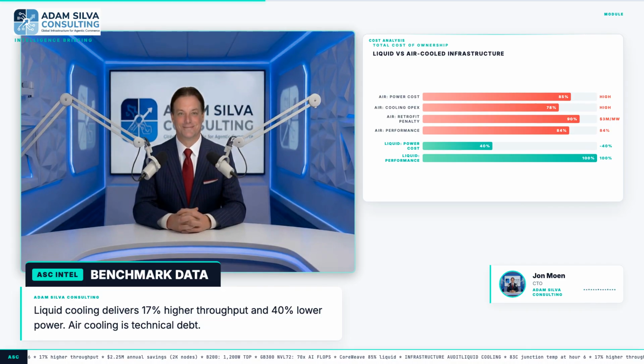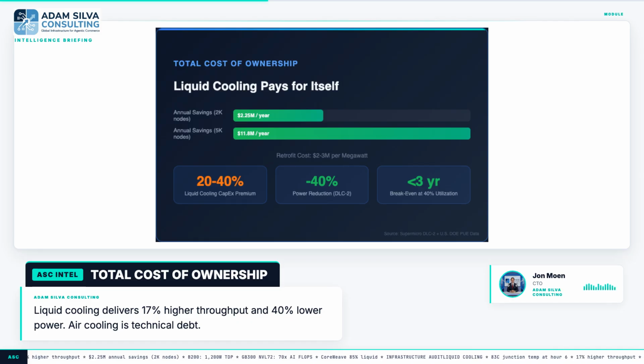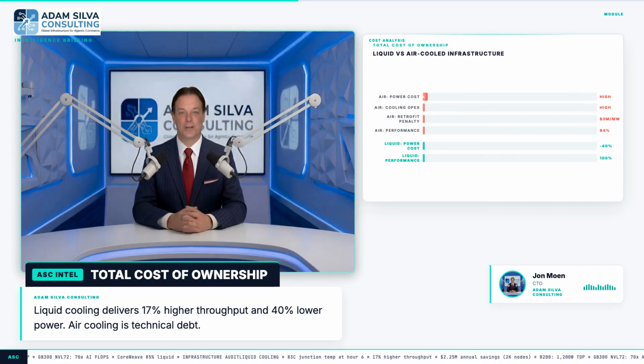That OPEX reduction closes the CAPEX premium on liquid cooling before the 3-year mark for any sustained workload above 40% GPU utilization. Is liquid cooling more expensive than air cooling? The upfront cost of liquid cooling is 20 to 40% higher than air-cooled equivalents, but the Supermicro DLC2 direct liquid cooling platform demonstrates 40% power reduction and 20% TCO reduction over a 3-year deployment horizon, making liquid cooling the less expensive option when measured.